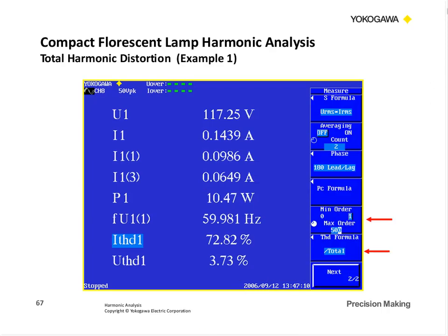So if we look at our harmonic analysis and we measure the THD, total harmonic distortion, we want to set the harmonic orders typically from the fundamental to the maximum order, which on this instrument was 500. And remember, the harmonic distortion, THD, is the square root of the sum of the squares of each of the harmonic components, and then we divide by, in this case, the total RMS value of the current.